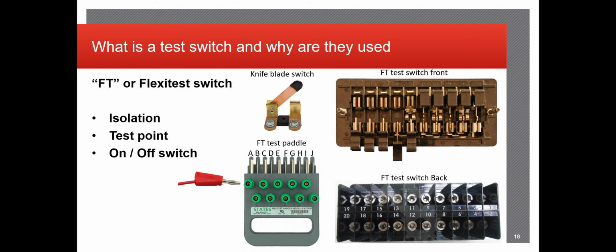There's a lot of different styles of test switches. This top right FT test switch front is the most common that I've seen and utilized, as well as the easiest for relay testing purposes in general, because it allows you to connect that FT test paddle, which you see in the bottom left there. That's a test paddle that we utilize for relay testing that actually just plugs right into the front of the test switch block, and you can connect your wires from your relay test set to the block itself, and it makes it very easy to move them around for different tests and whatnot.